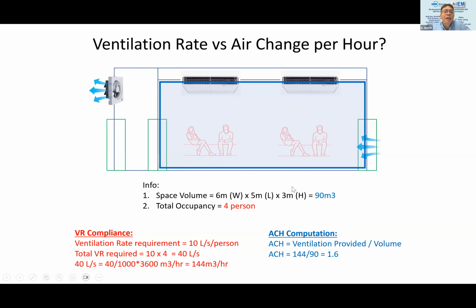So if you understand, air change per hour and outdoor air rate are interrelated. Okay, if you still cannot compute by yourself, use the MVC. You key in the dimensions, you key in your required fresh air, and you get the ACH as well as the direct outdoor air or the equivalent outdoor air that is being provided.